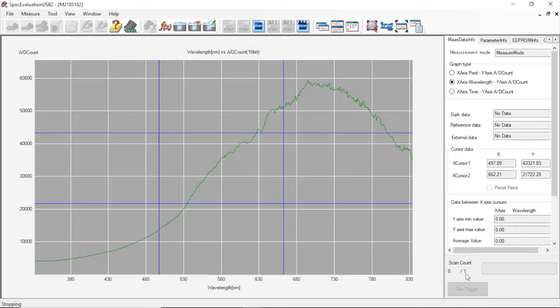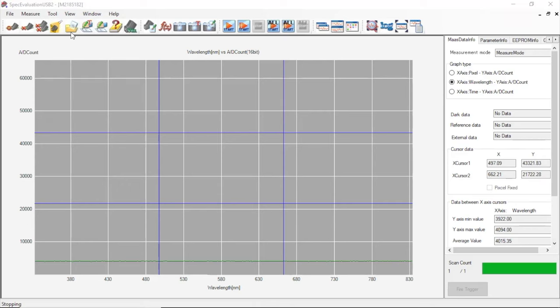As we can see on the right, this gauge shows only one scan is being logged. With the gauge filled, we know the measurement is complete and we now need to assign this data as our dark data. We'll do so by going over to tool and selecting arithmetic. So this tab ensures that the file that is saved reflects the most recent data or the present measurement as the dark data. This can also be used for reference when applying functions such as dark subtraction.